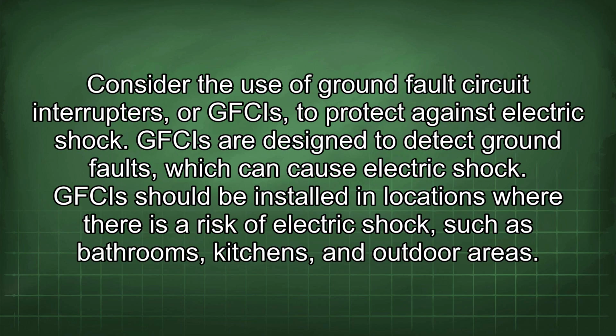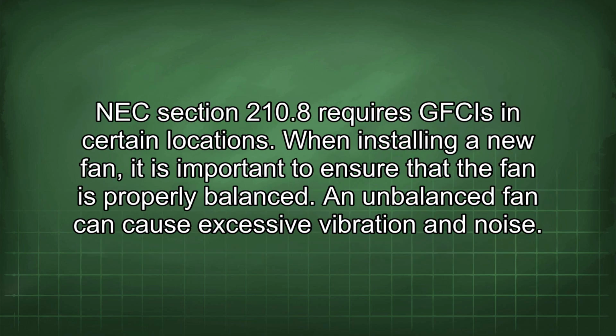Consider the use of ground fault circuit interrupters, or GFCIs, to protect against electric shock. GFCIs are designed to detect ground faults, which can cause electric shock. GFCIs should be installed in locations where there is a risk of electric shock, such as bathrooms, kitchens, and outdoor areas. NEC Section 210.8 requires GFCIs in certain locations.